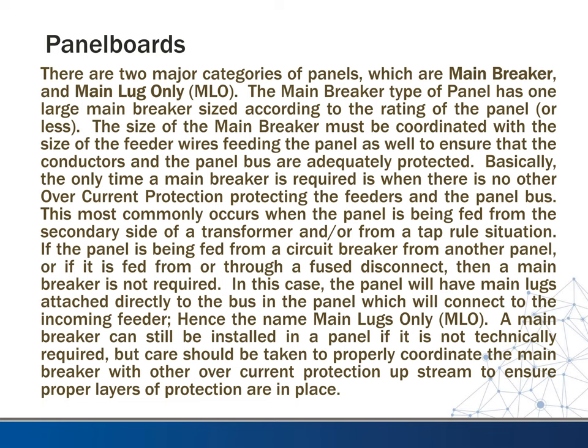Basically, the only time a main breaker is required by code is when there is no other overcurrent protection protecting the feeders and the panel bus. This most commonly occurs when the panel is being fed from the secondary side of a transformer and/or from a tap rule situation. If the panel is being fed from a circuit breaker from another panel, or if it is fed from or through a fuse disconnect, then a main breaker is not required, although you can still have one.